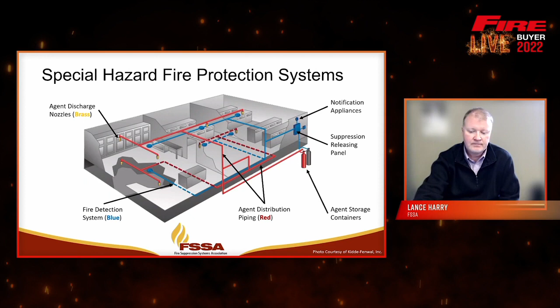So as I mentioned, a couple of pictures here. Traditional gaseous systems would look something like this, where you'd have agent storage containers, pressurized containers stored in a bunch. Could be one, two, three, or a whole bank of cylinders, depending on the size of the space you're protecting. You could install these cylinders in the protected space itself, or in a remote location, with the agent piped into the protected space, as we saw in the previous slide.